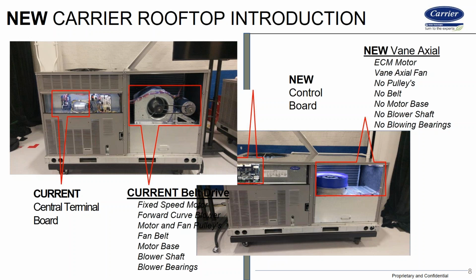That's why you've got to know what your external static is up front, and then set it accordingly with the switch and the potentiometer. But great question. This particular setup right now doesn't do that. What I'm going to talk about a little later is a new unit coming down the pipe that is basically this unit, but a full inverter driven unit. So we'll have wider control of airflow on the supply side. We'll have control of airflow with a condenser fan and of course an inverter driven compressor. I'll mention some of the highlights on that in a little bit, but thank you for the question. That's a great question.